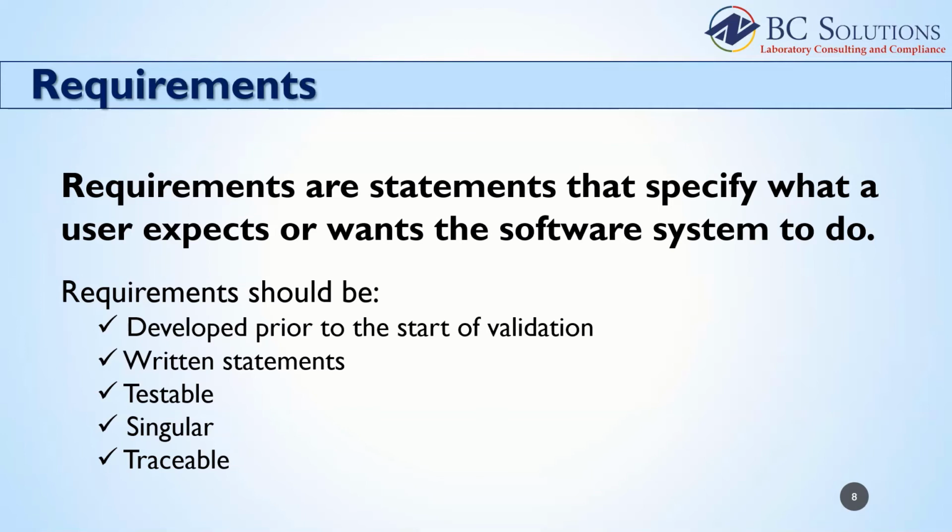That is up to you to determine based on your facility's needs and functions and use. You might begin by using your original request for proposal specifications that listed what you wanted a computer system to do. You can use regulatory documents such as the AABB record-keeping standards or FDA guidances to develop your requirements. Vendor documentation should detail the critical control points of the software. You want to make sure you include requirements and test cases to verify the system performs as specified by the vendor.